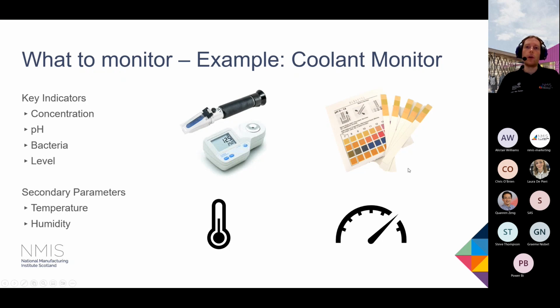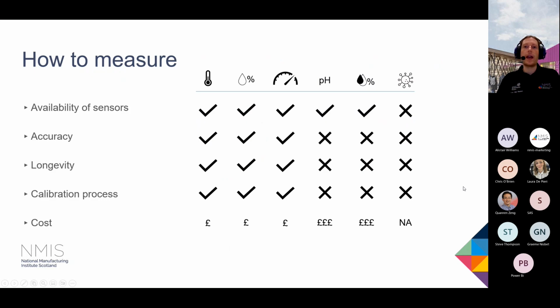Okay, so now that we know what we want to monitor, the next question is, how do we want to measure that? The first thing to consider when you're looking at how you measure something, bearing in mind that we're talking about digital in this case, is whether there is some kind of digital sensor available to measure that parameter. Once you've identified what sensors are available, your next question is accuracy. Just because you can get an indication or some kind of electrical signal to indicate something, it doesn't mean that that signal is accurate or giving you any valid information. So you need to verify that what you're getting is good.